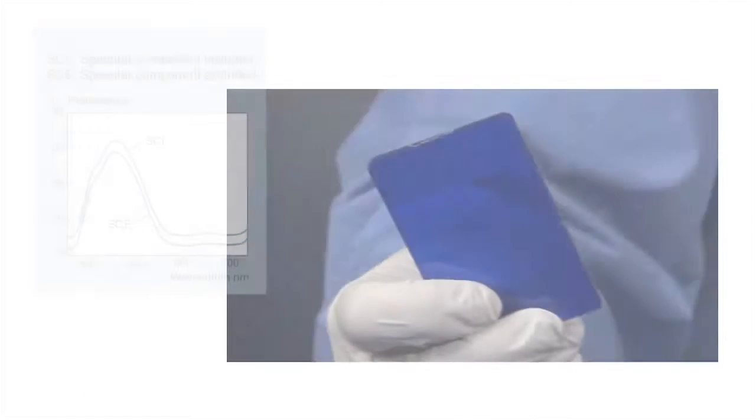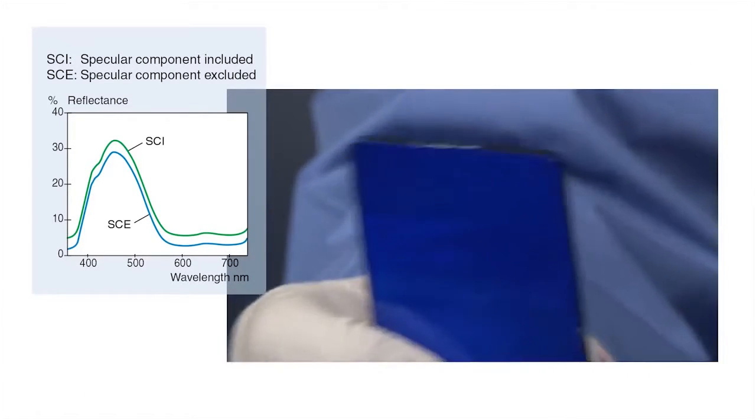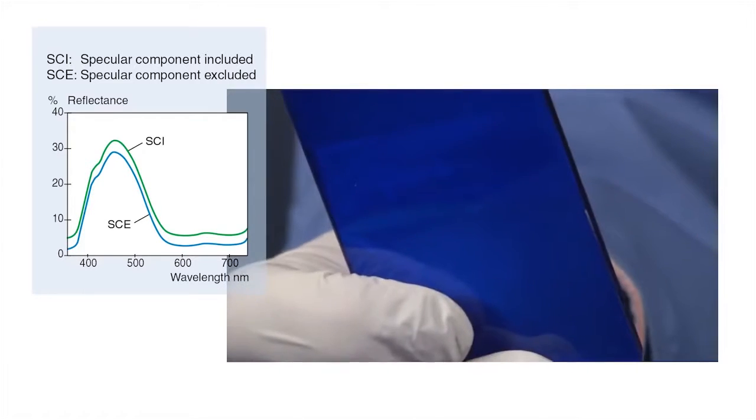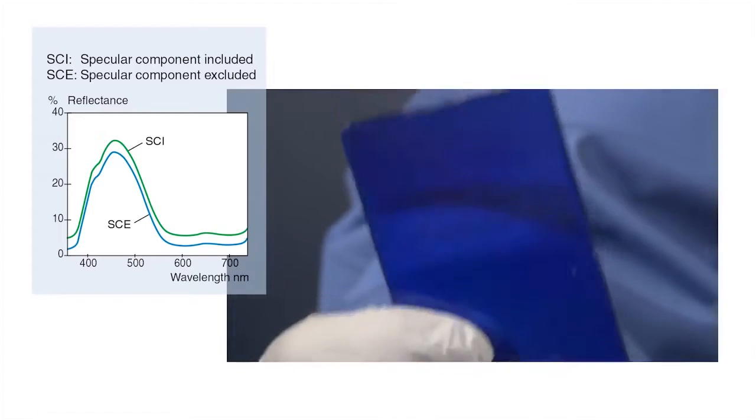By using two xenon lamps, the system can provide simultaneous color measurement results for specular components included, SCI, and specular components excluded, SCE, with just a single measurement.